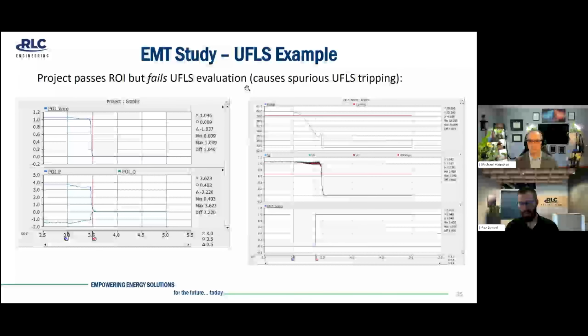So to give you a quick graphical example, hopefully this one is easy to understand, but on the left side here, you have that same event that I showed you for the ROI pass scenario a couple slides ago. As a reminder, you have an event at 3 seconds, and at 3.5, or 0.5 seconds later, your project trips offline and it's not an issue. However, the right plots would indicate an UFLS failure due to a nuisance trip. So what you have up here, F-measure or measured frequency, and this horizontal red line is F pickup, or the under frequency load shed pickup, right at about 59.1 hertz or so. So essentially what happens here is if the frequency goes under this frequency pickup for a certain amount of time, then the UFLS would look to activate.